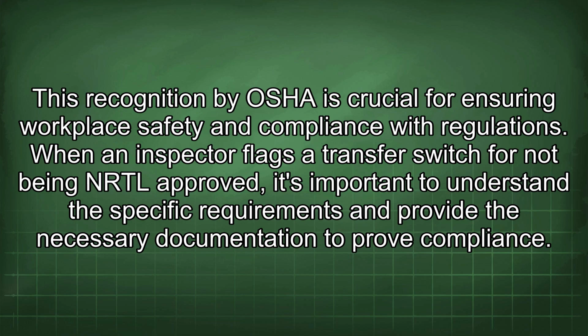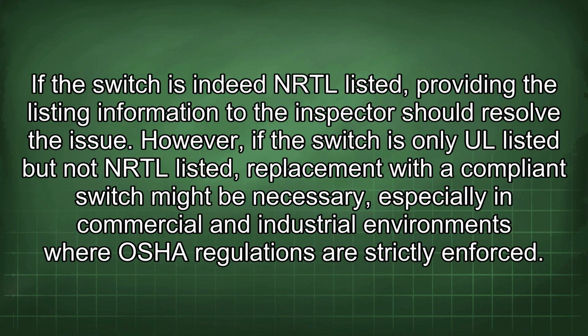When an inspector flags a transfer switch for not being NRTL approved, it's important to understand the specific requirements and provide the necessary documentation to prove compliance. If the switch is indeed NRTL listed, providing the listing information to the inspector should resolve the issue. However, if the switch is only UL listed but not NRTL listed, replacement with a compliant switch might be necessary, especially in commercial and industrial environments where OSHA regulations are strictly enforced.